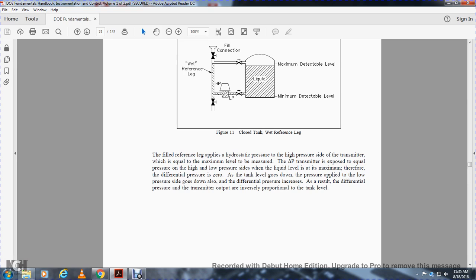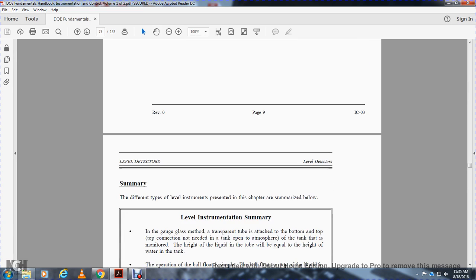As the tank level goes down, the pressure on the low side goes down, but the high pressure side stays constant. Differential pressure increases as a result, and the differential pressure transmitter output is inversely proportional to the tank level.